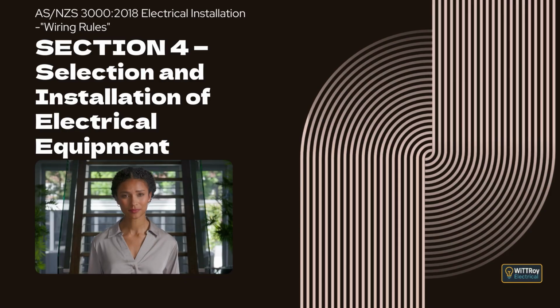Capacitors and electrical equipment containing capacitors must be provided with a warning notice advising that capacitors must be completely discharged before working on the equipment. Clause 4.15.3.2, Capacitors connected in parallel with individual appliances. Where a capacitor is connected in parallel with an individual appliance, it must be connected so that the windings of the appliance provide a permanent discharge path for the capacitor, and no switch or fuse is permitted between the capacitor and the appliance. These requirements do not apply where the capacitor incorporates a permanently connected discharge device. In this arrangement, the capacitor is regarded as being controlled by the control gear of the appliance.